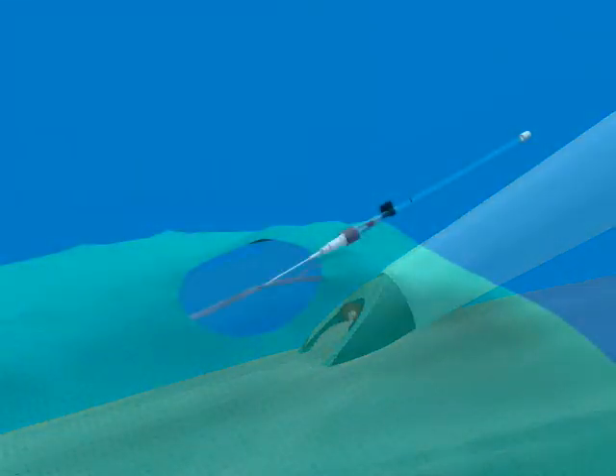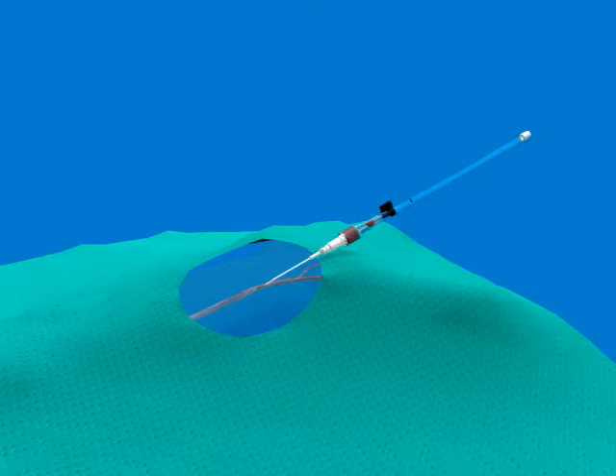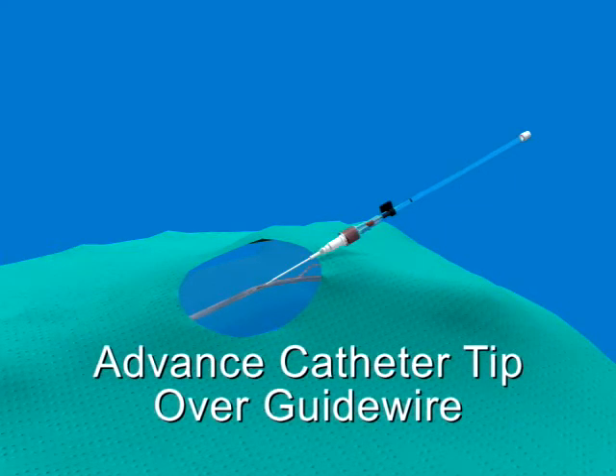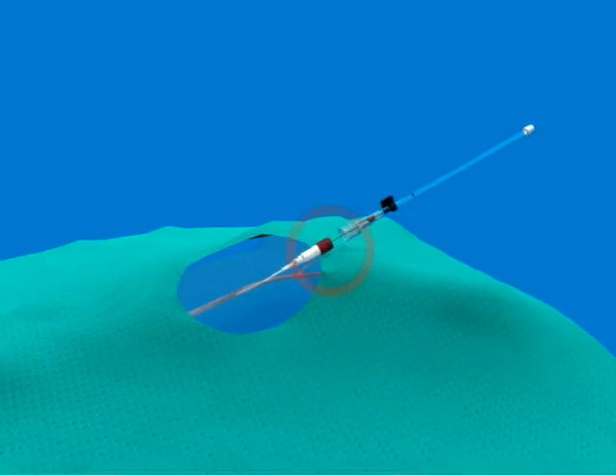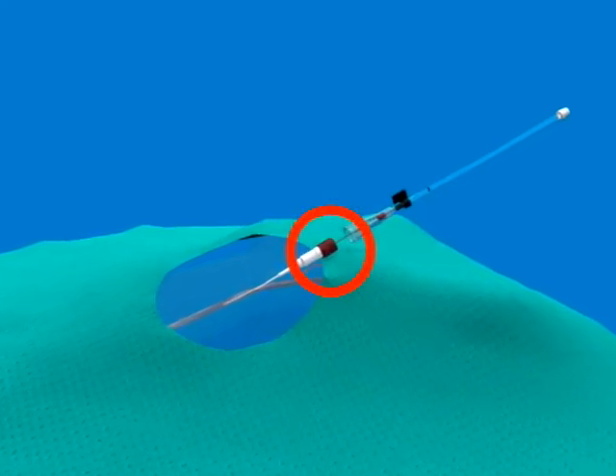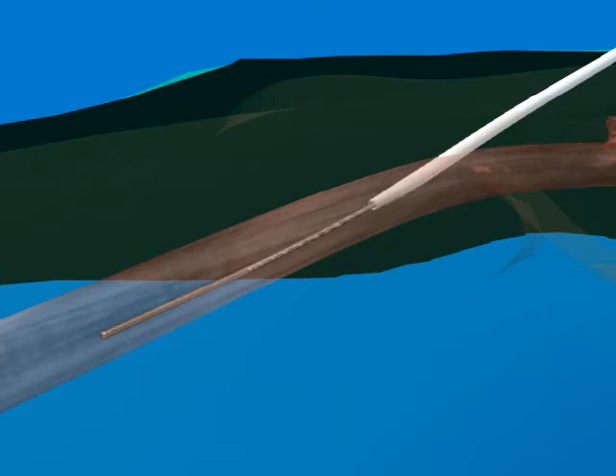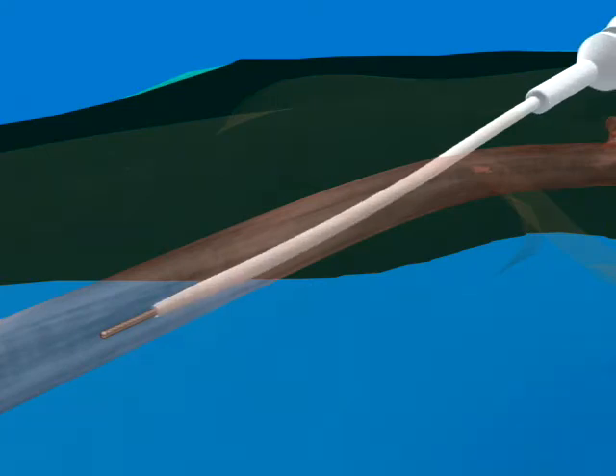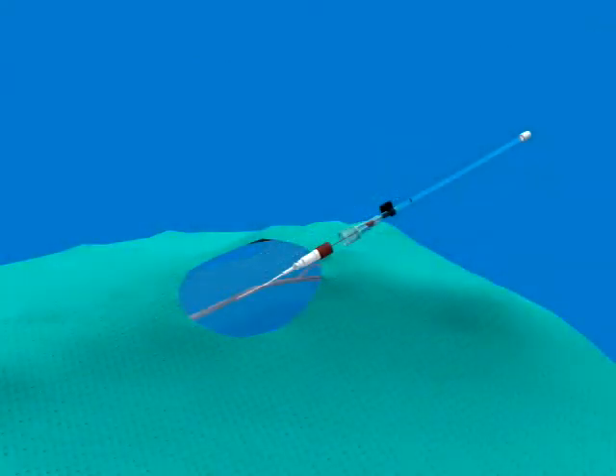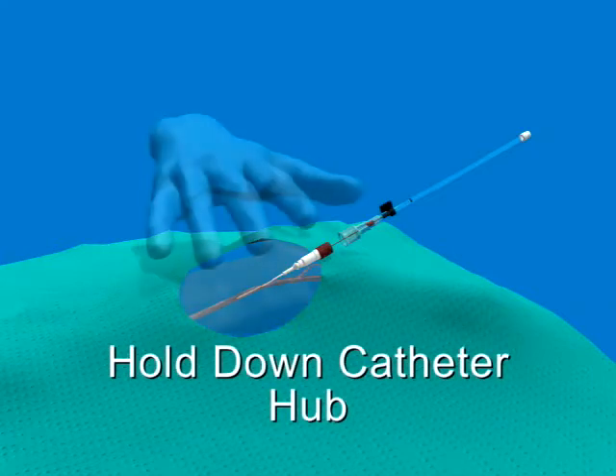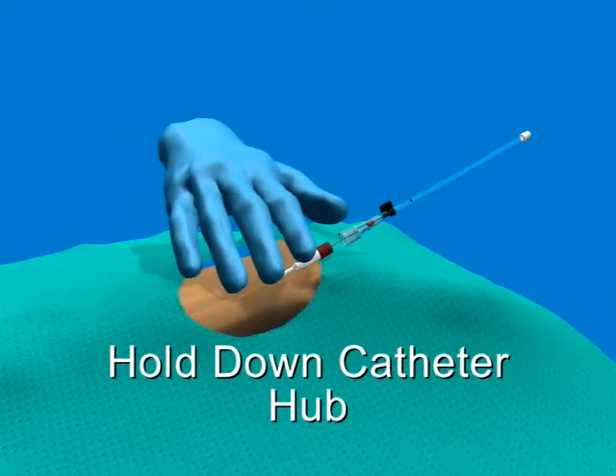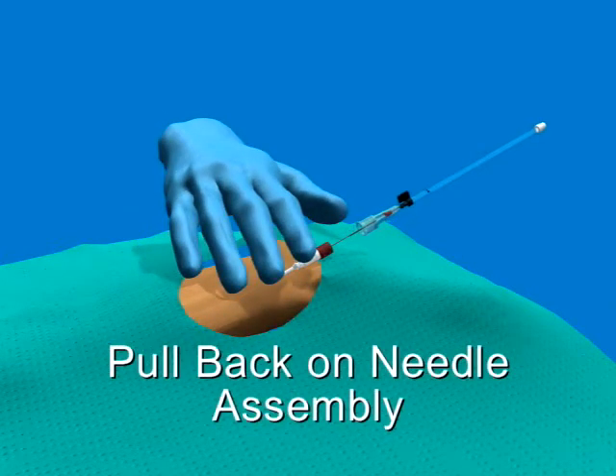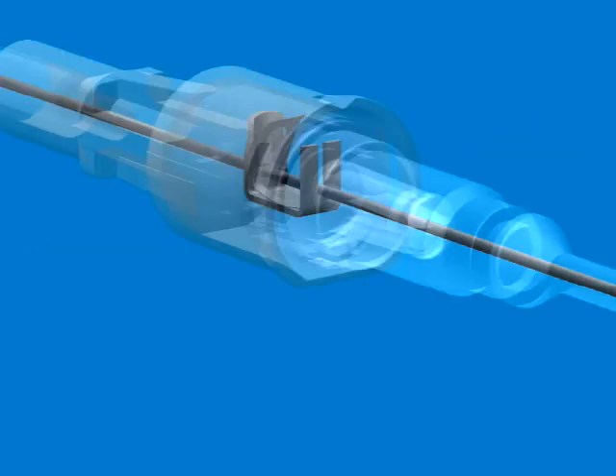While holding the introducer needle hub, the clear hub that covers the red safety hub, advance the catheter over the spring wire guide. As the catheter advances, the red needle protection cap will follow and will remain locked onto the catheter hub until the needle enters the protection device. Secure the catheter hub and continue to pull the needle hub. The needle tip will be locked into the protective assembly when the needle is pulled out of the catheter hub.